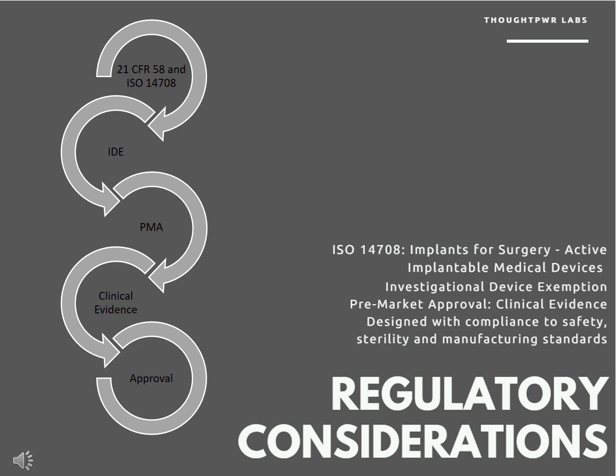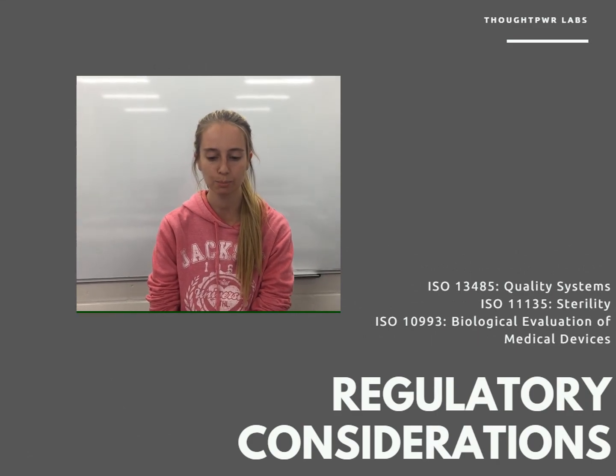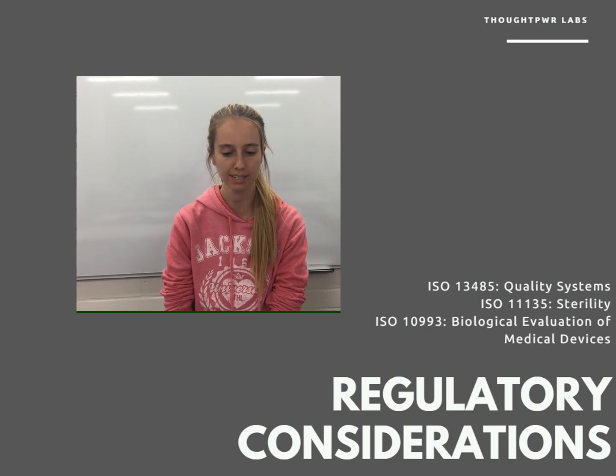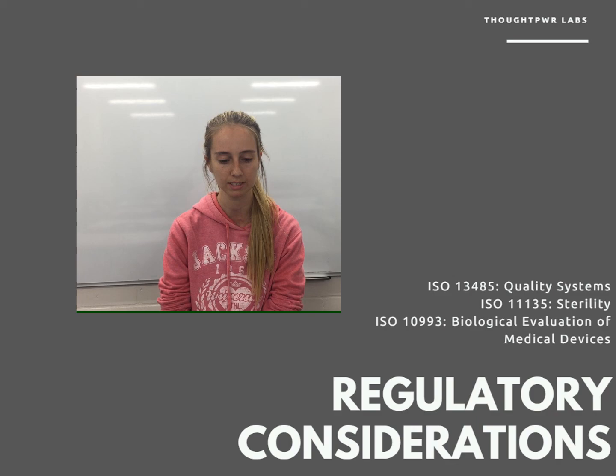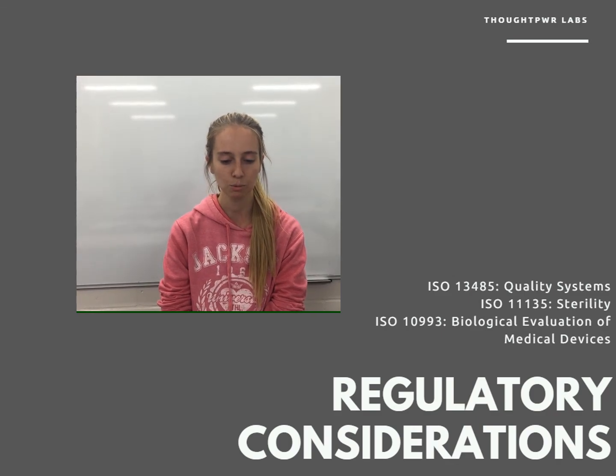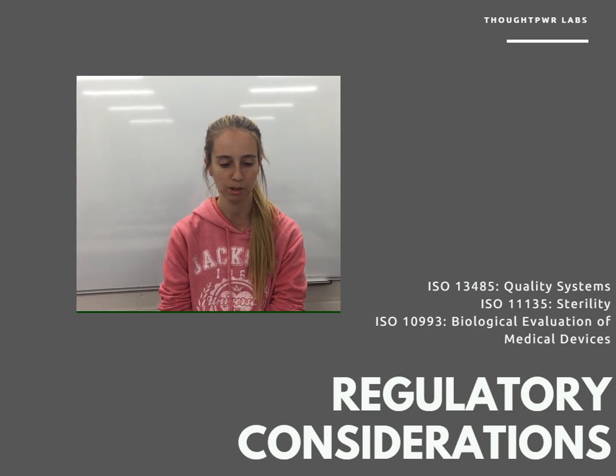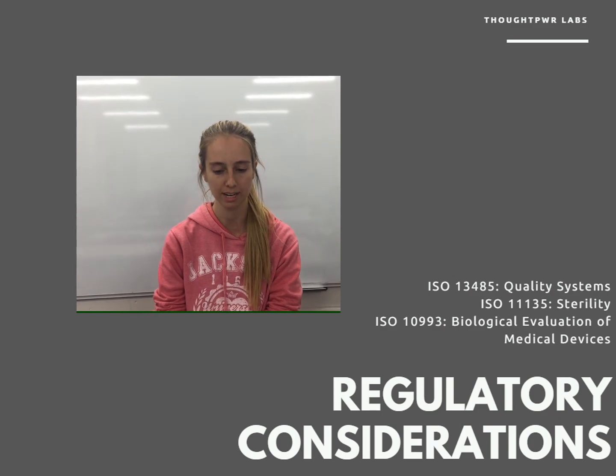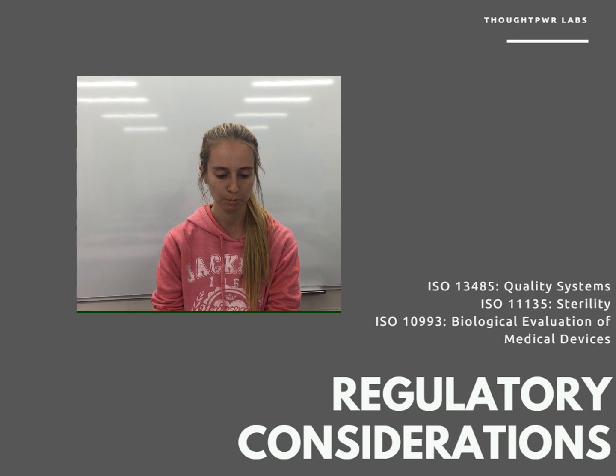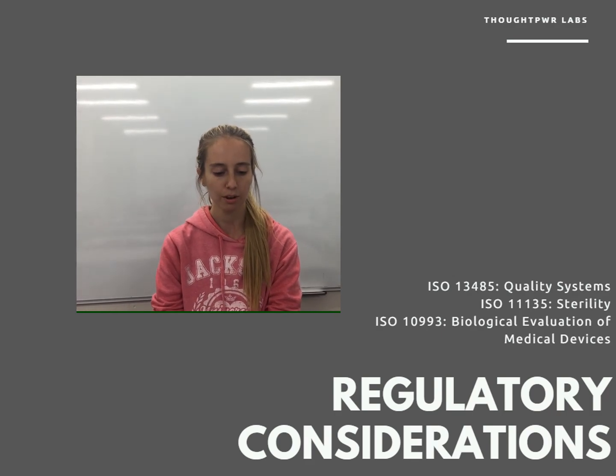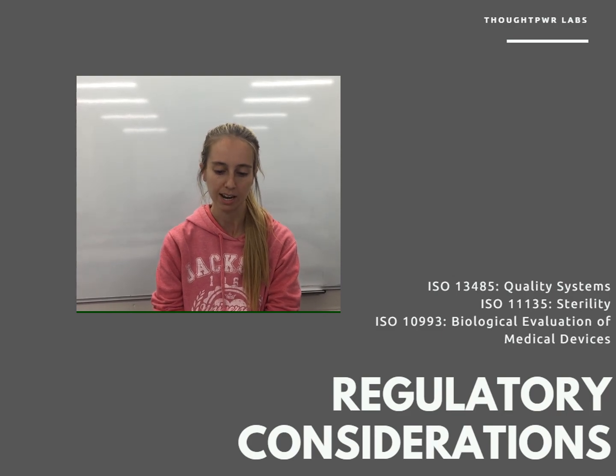Safety, manufacturability, and biocompatibility of nitinol has been proven by past literature which indicates that other neurological medical devices comply to FDA regulatory standards. While currently there are no stentrodes on the market, clinical trials are being performed to assess the safety and efficacy of other similar devices. The major regulatory challenge for our device is the approval of the novel manufacturing process of the nitinol used, as the device has a similar mechanical design to devices that are currently in clinical trialing phases of regulatory approval. With this in mind, our team will undertake testing to ensure that the electropolishing process has compliance to safety, efficacy, quality management, and manufacturing standards such as ISO 13485, ISO 11135, and ISO 10993. Verifying reliability over device lifetime and structural integrity is something our team is working towards.